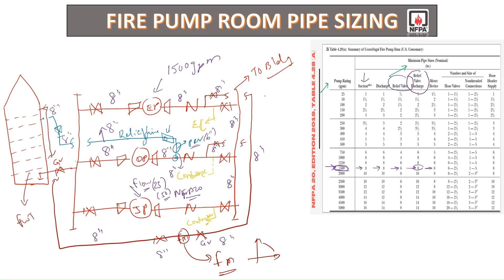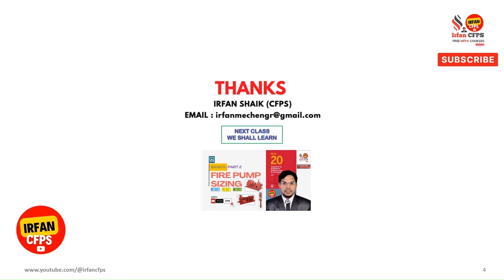Apart from that, we have hose valves and hose header supply, which I will discuss later. We can also consider 8 inch size for the suction header. The gate valve on the suction side of the tank will be 8 inch and the suction header will also be 8 inch. I hope you understand how to determine the pipe sizes based on the fire pump capacity. If you have any comments or clarifications, you can contact me through my email or comment in the comment section. In the next class we are going to determine the fire pump capacity itself — till then, bye.